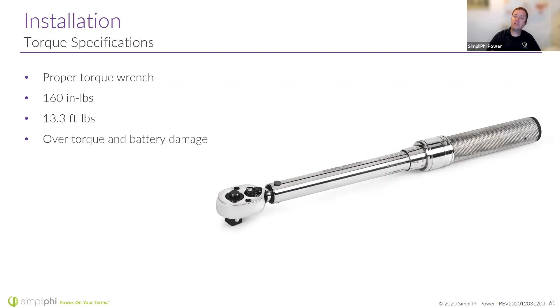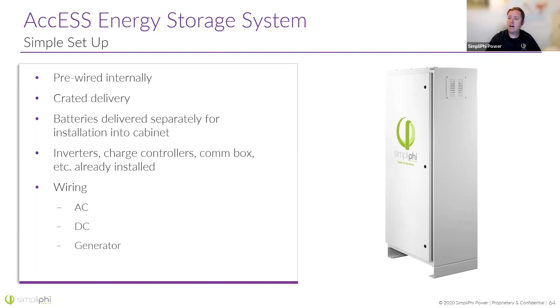I'm going to finish off on access before we talk a little bit about the IQ program. I talked about it a little bit earlier. This energy storage system with that 9540 UL listing comes pre-wired and pre-programmed. Make sure you check that programming before you turn it on, just in case something happened in shipping. The batteries come separate, so you'll have to install those batteries and get your torque wrench out to make those final battery connections. But it has everything you need inside.